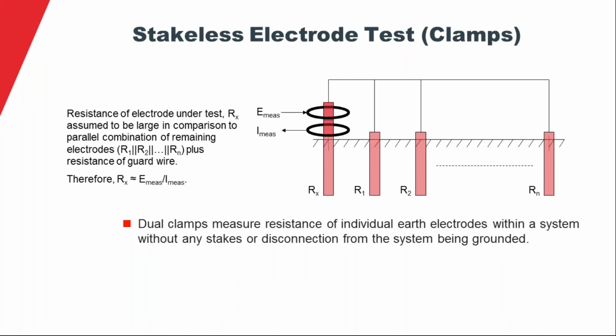The main drawbacks to it are shorts and opens. If you have a short, that would be if your grounding electrode is connected to the electrical system at more than one point, which a lot of them are. And if that happens, then your test current is going to just travel around to all those other ground connections and loop back, and you'll get a beautiful low reading, and it's wrong because it's only telling you what the continuity of the metal is. So you can't use it there. And the other thing is an open, which would be basically a new ground that hasn't been connected to the utility. There's no return path for the current to come back and give you a measurement, and the tester will show you an open circuit. People do sometimes jury-rig temporary returns so they can do this. There's really nothing wrong with that, except that it does kind of defeat the purpose of having a Clamp-On in the first place. So those are your two advanced technologies, ART and Clamp-On.